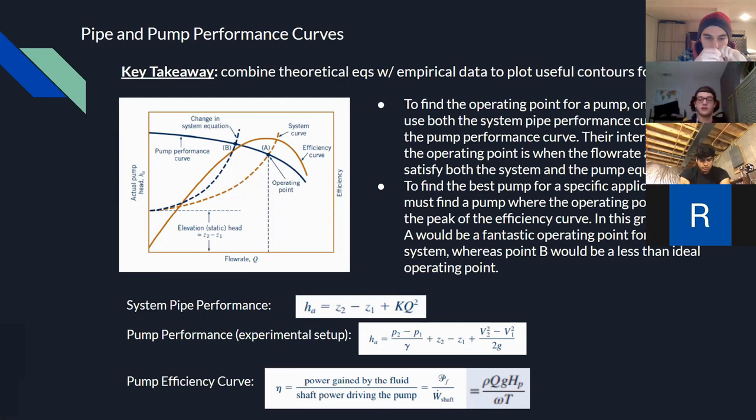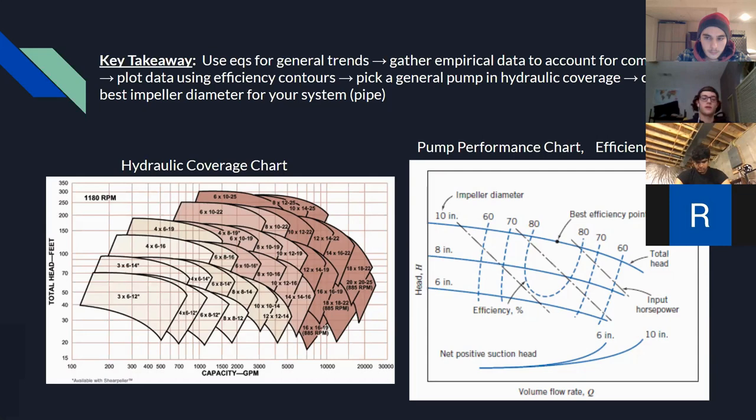To find a pump for a specific application given head and flow rate, we can use the hydraulic coverage chart to find the size of the pump needed, and then we can use the pump performance chart as a zoom-in tool to find the size of the impeller blades for that specific application.